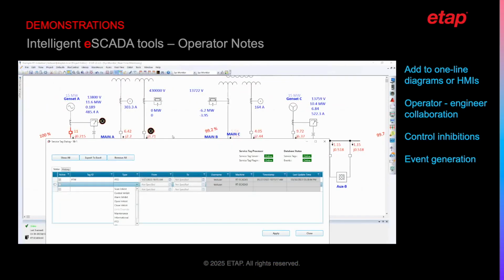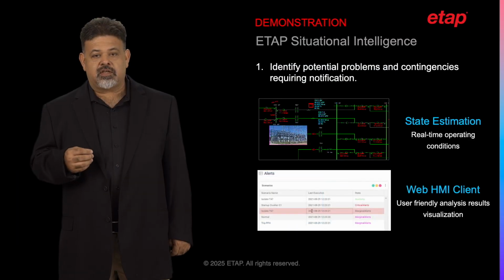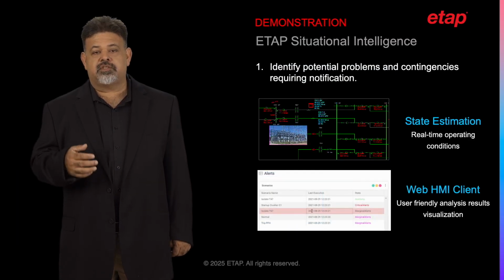Operator Notes allows the operator to create notes regarding components directly in the one-line diagram or HMI in the system. This is a powerful tool that can be used to improve communication between operators and engineers. It allows them to share important knowledge, such as equipment service states, including maintenance. These actions can be paired with temporary inhibitions, such as alarms, control, or scan inhibits, to protect the operation for a specific period. Finally, let's take a look at the ETAP Situational Intelligence feature.